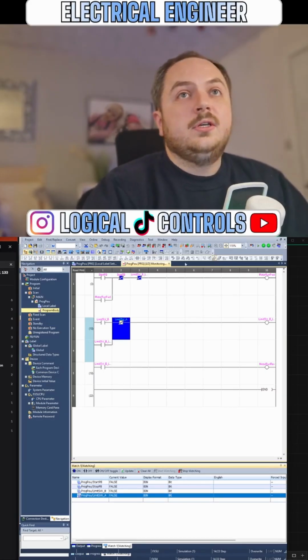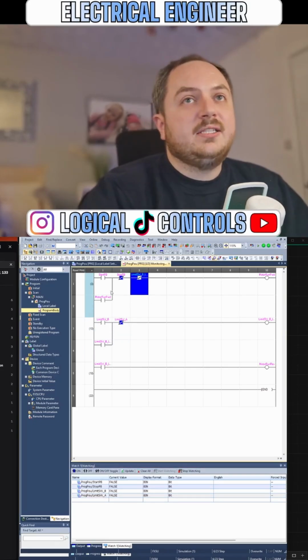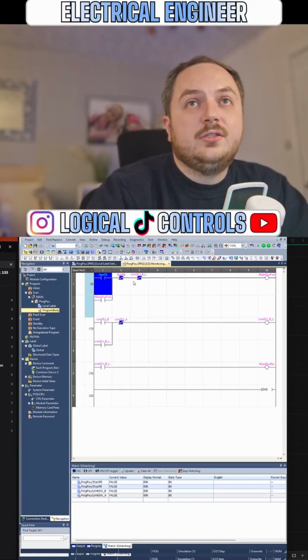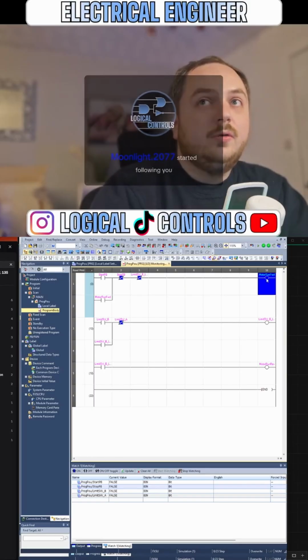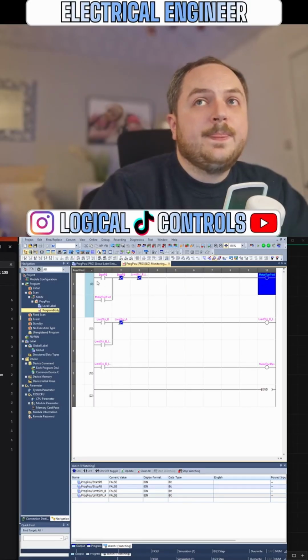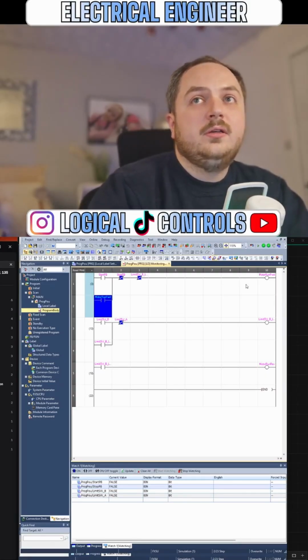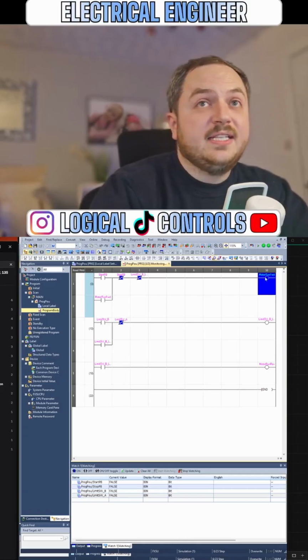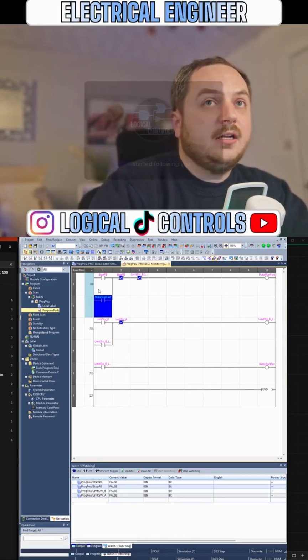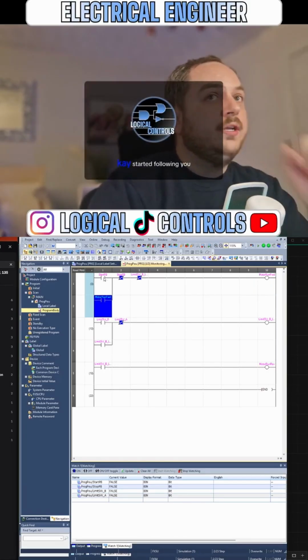Hopefully that helps, so to go through it step by step: this is the start button, we've got a standard latch circuit. As soon as you press that, you're going to get a logical true all the way along here until you hit this coil, which energizes. If you take your finger off the start button, you need the latching - the minute this energizes, this contact closes, so when you take your finger off the button and it goes back to normally open, you've got a pathway down here.